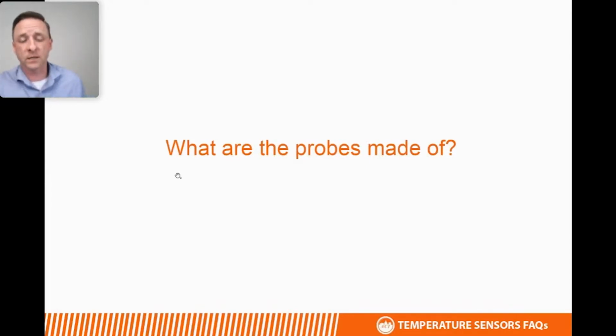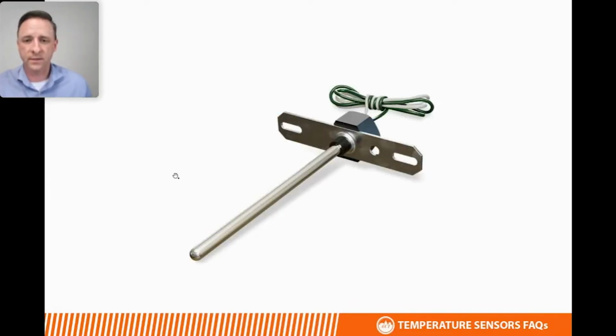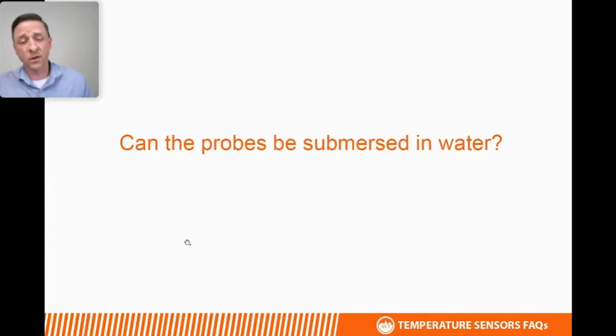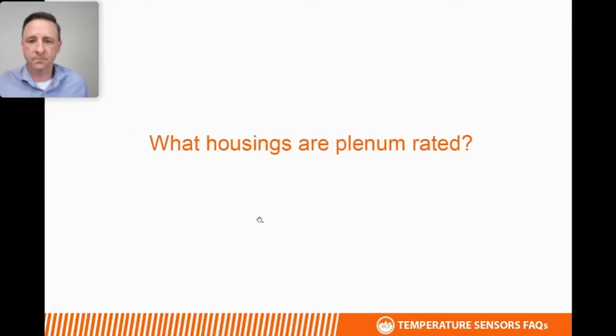These probes are made of a solid, one-piece 304 stainless steel probe or tube. There are some competitive parts out there where the probe is like a cylinder with a cap that's crimped or glued together. Our probes are not of that style. It's a one-piece 304 stainless steel. As such, the tip of that probe could be submerged in water, but the entire probe is not submersible. If water gets into the backside of that probe or were to fill that probe, that is likely to lead to a sensor failure, but the tip of the probe is watertight.